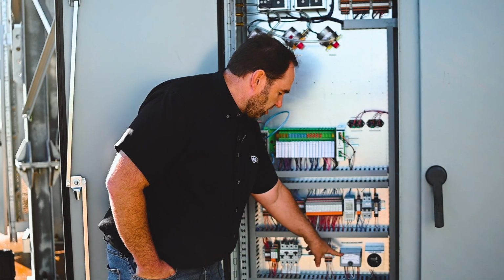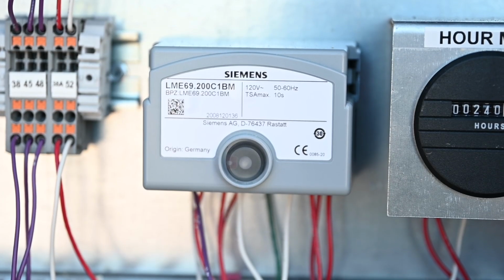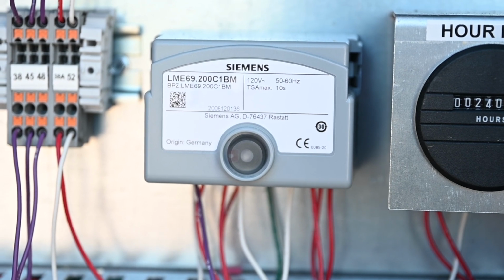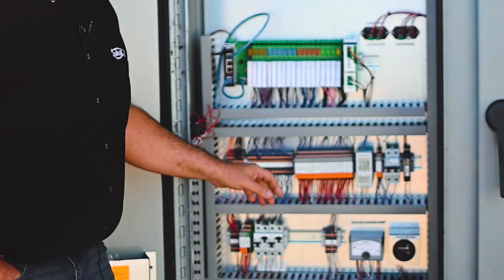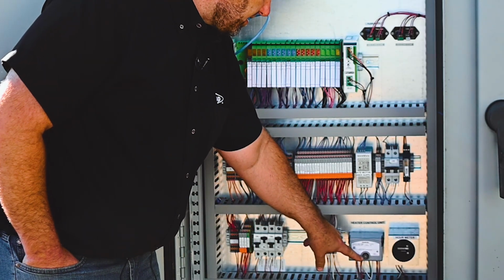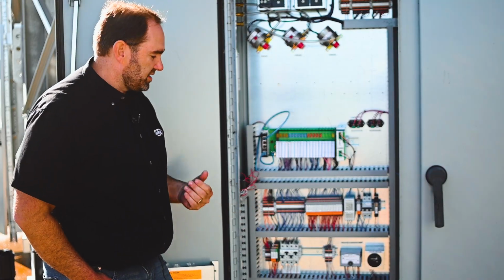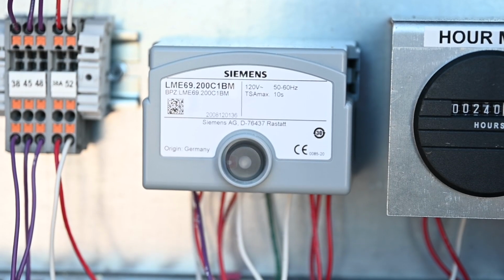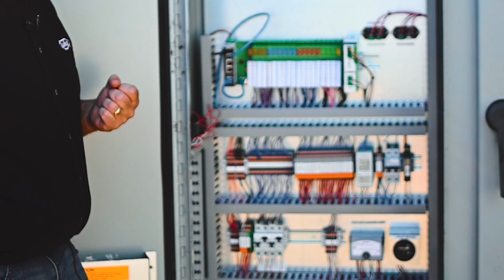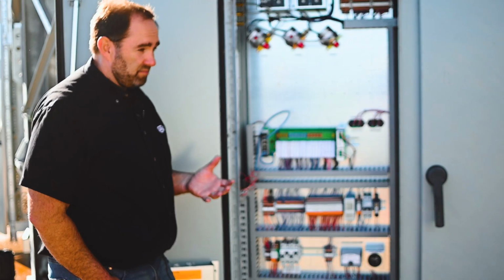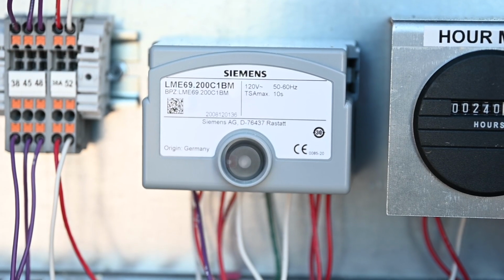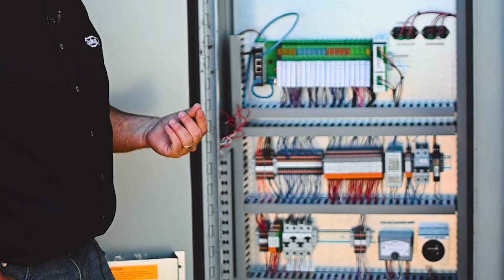This is a Siemens burner controller. This one is an LME69 series. We're also using LME71 series controllers now. There is a light on these, and the light means some different things. If it's red, it means it's in a lockout condition. When the burner is lighting or going through a purge cycle, you'll see it in a yellow position. When it's actually in the lighting cycle, it'll be blinking yellow. If it does sense flame, it'll turn green.